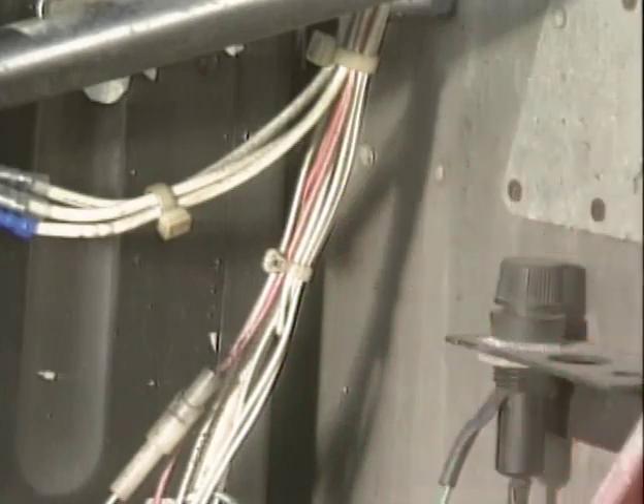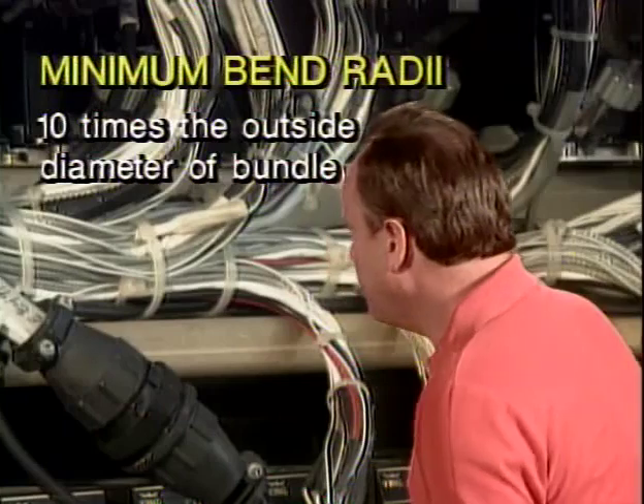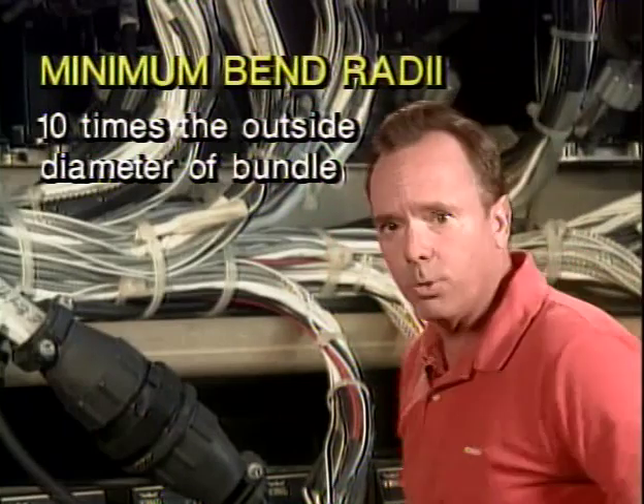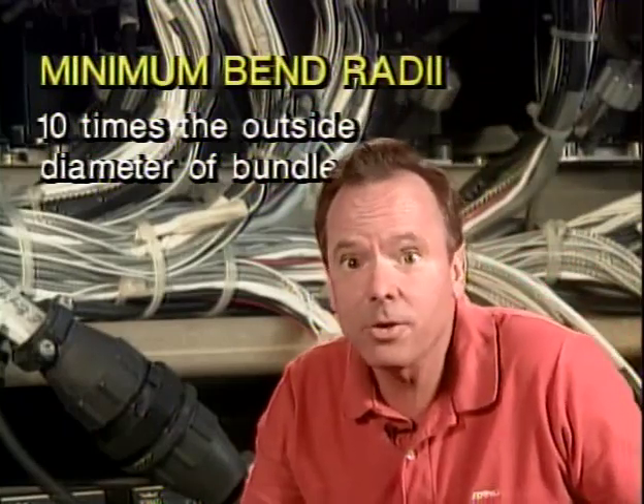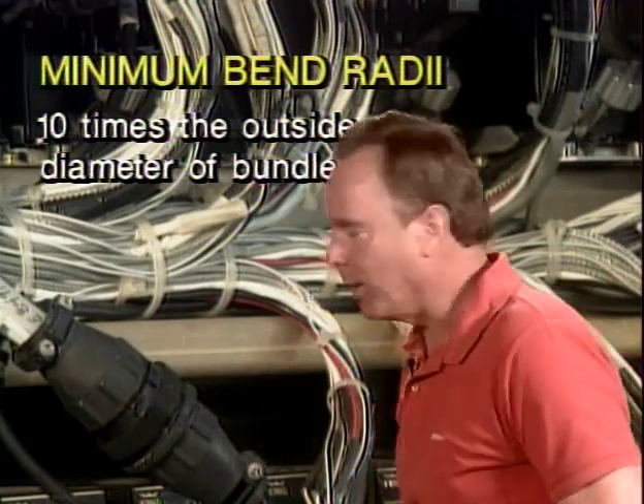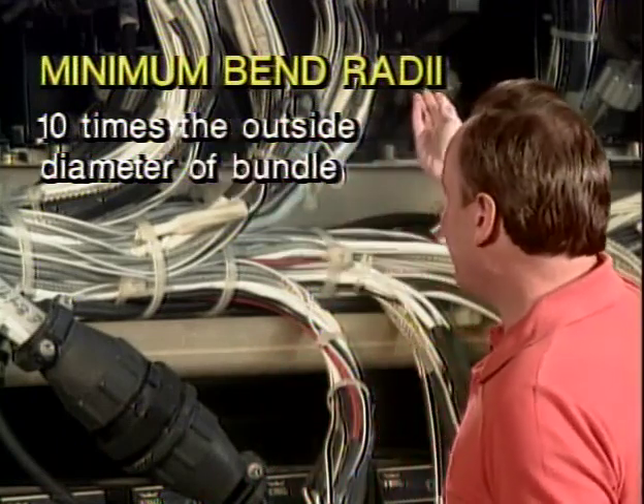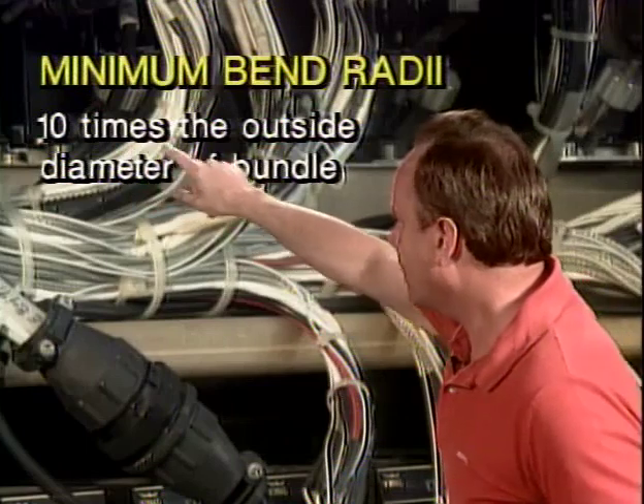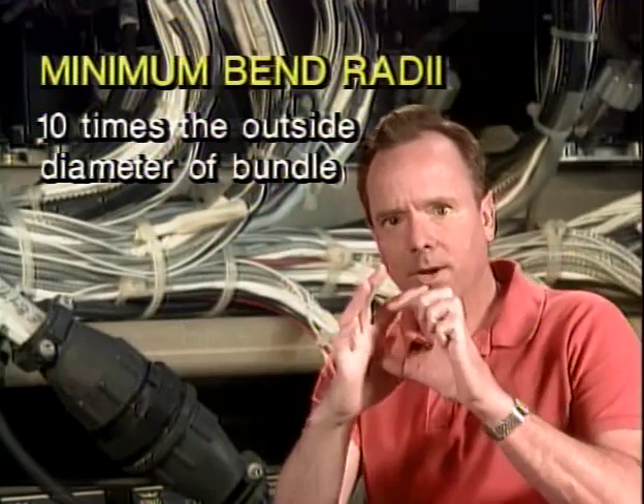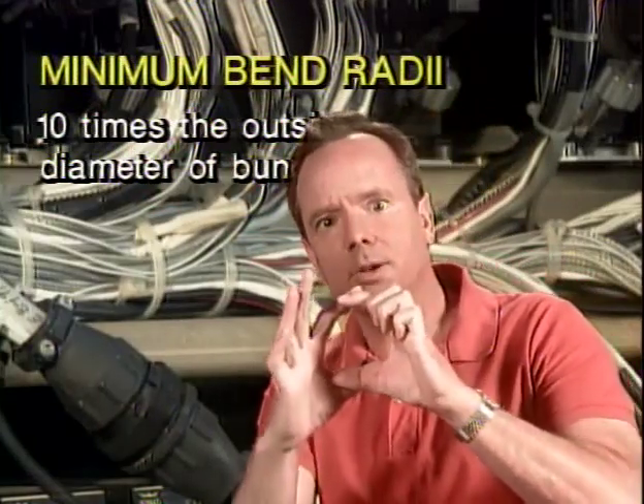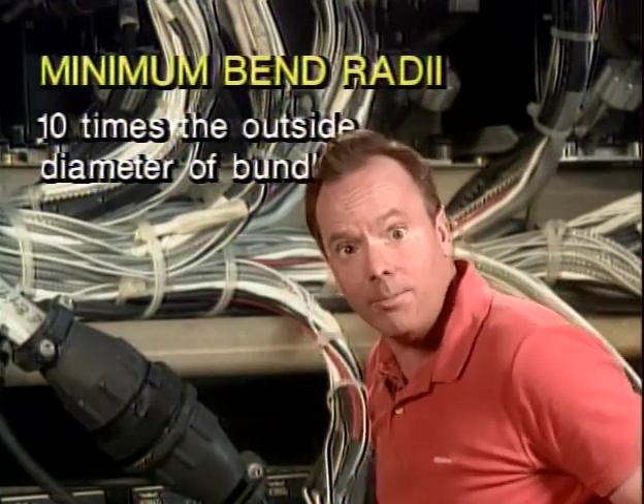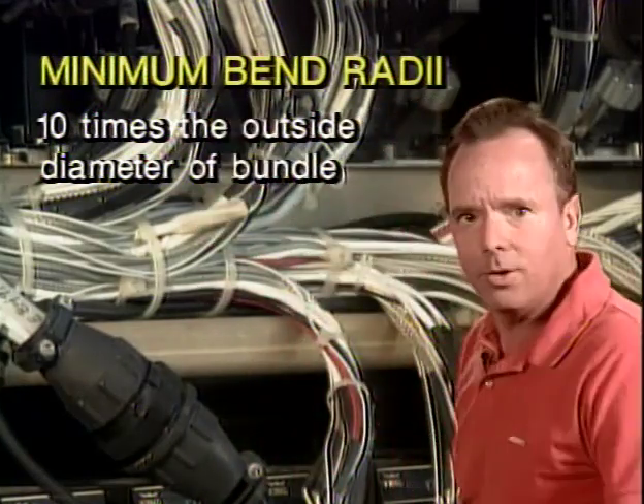Now, let's talk about the minimum radius of a bend in a wire bundle. They're going to kind of confuse you just a little bit on the test, and they're going to refer to a minimum bend radii. That means more than one radius. There's two of them. That's all they're doing right there, or at least more than one anyway. So the minimum bend radii should be 10 times the outside diameter of the bundle. Figure out the outside diameter of the bundle and multiply by 10, and that is the minimum bend radii.